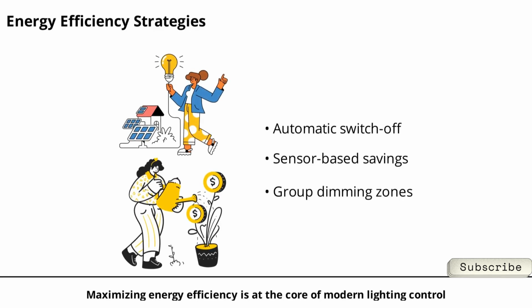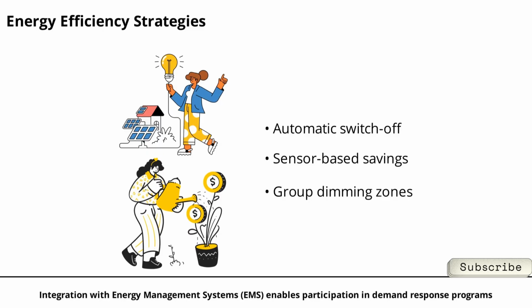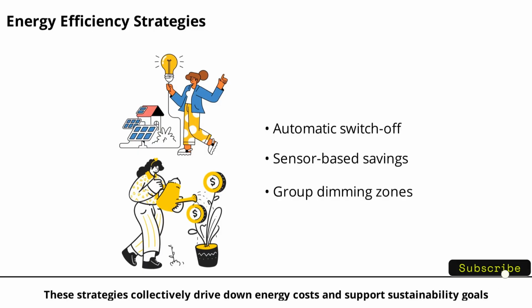Maximizing energy efficiency is at the core of modern lighting control. Strategies include automatic switch-off to prevent unnecessary usage, combining occupancy and daylight sensors for maximum savings, and grouping dimming zones to optimize lighting based on space use. Integration with energy management systems, EMS, enables participation in demand response programs, while time delay controls ensure lights remain on briefly after a space is vacated. These strategies collectively drive down energy costs and support sustainability goals.